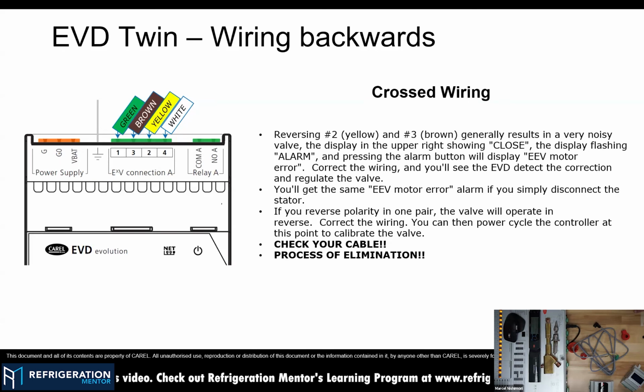Sequences of wires, again, this is something that we discussed, and what happens if you have different sequences. Make sure that you check here, because CAREL has the sequence of wires connected for poles of the stator. So 1 and 3 is the first pole, and 2 and 4 is the second pole. That's why we have a 1, 3, 2, 4 sequence of wires and not 1, 2, 3, 4. Make sure that you have the right sequence, because if you reverse brown and yellow, you are into different windings, and it means that you have a motor error, so the controller cannot read the coil.